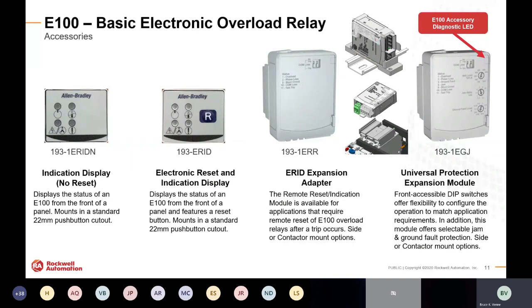Then we have the Universal Protection Expansion Module, which offers ground fault and jam protection for the E100, again connecting to that expansion port. This is very similar to the reset adapter and can be mounted in a similar fashion, on its side or on the front of a Bulletin 100C contactor. You have access to different dip switches and rotary dials to configure this component and enhance additional protection for your overload solution.